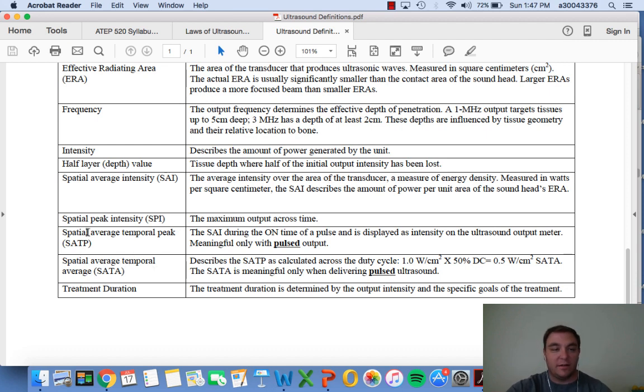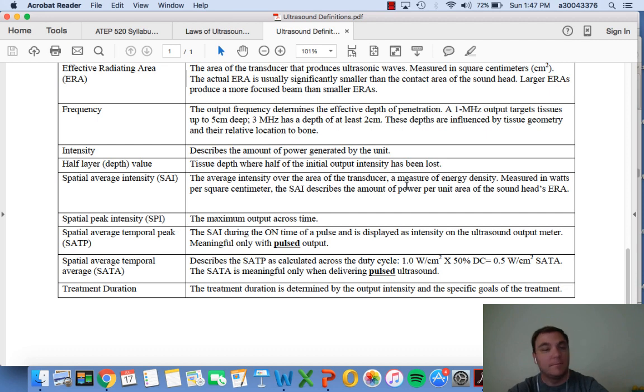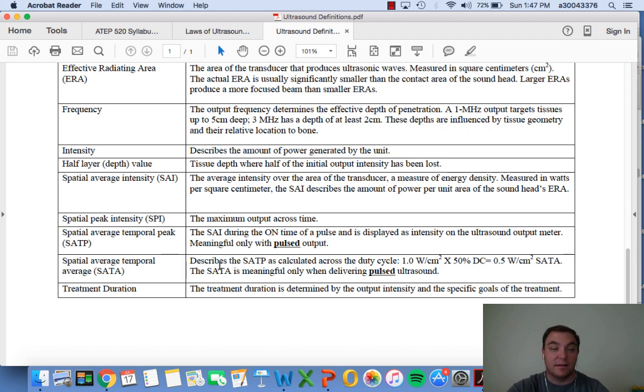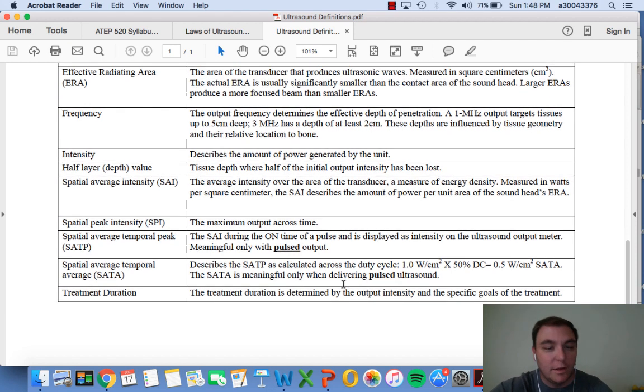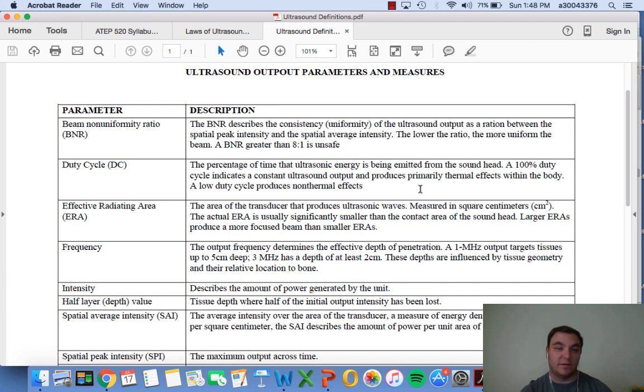To understand temporal average, we need the SATP - spatial average temporal peak - the spatial average intensity during the on-time of a pulse, displayed on the ultrasound output meter. This is only meaningful with pulsed ultrasound. The spatial average temporal average (SATA) describes intensity calculated across a duty cycle, and is also only important during pulsed ultrasound. A duty cycle is the percentage of time the ultrasonic energy is being emitted from the sound head.